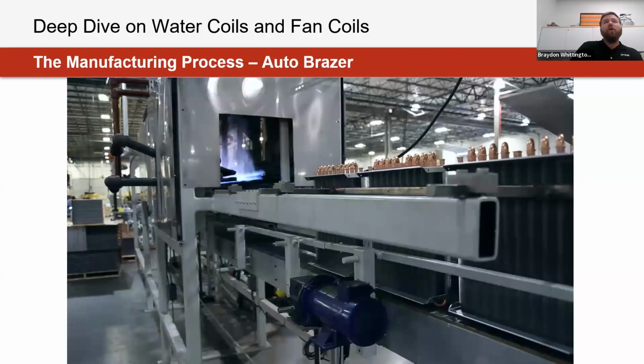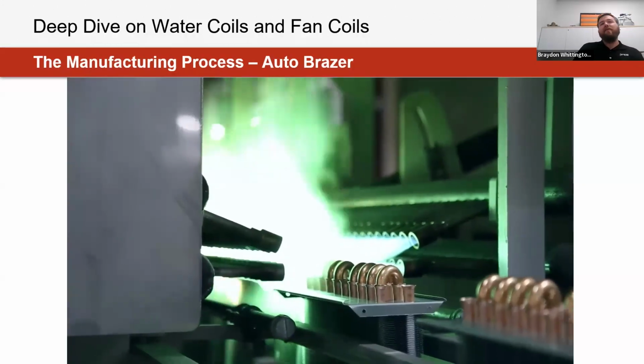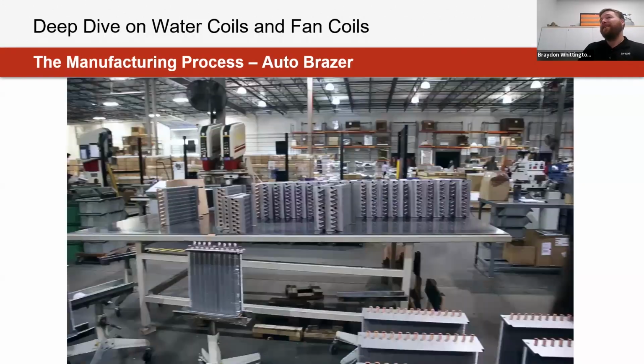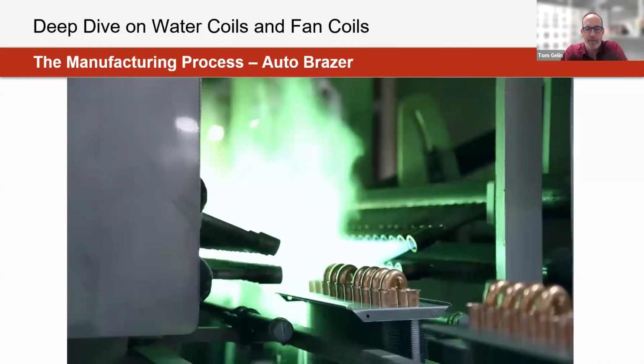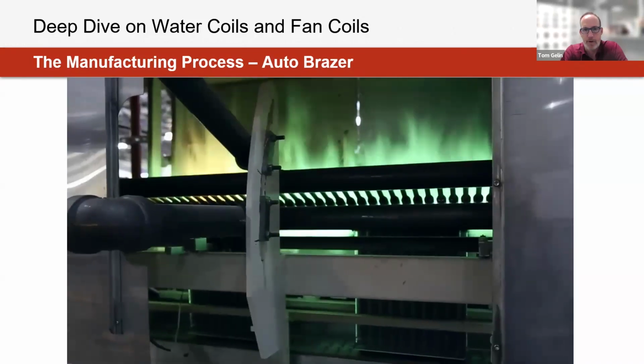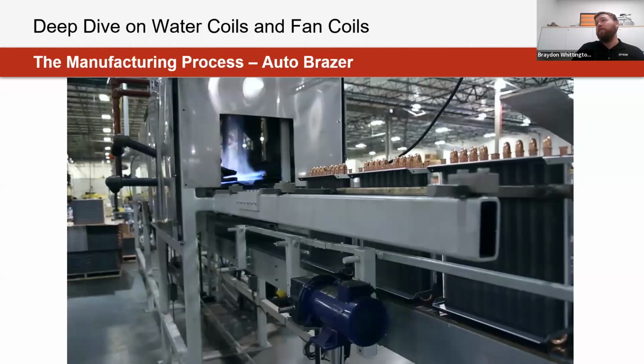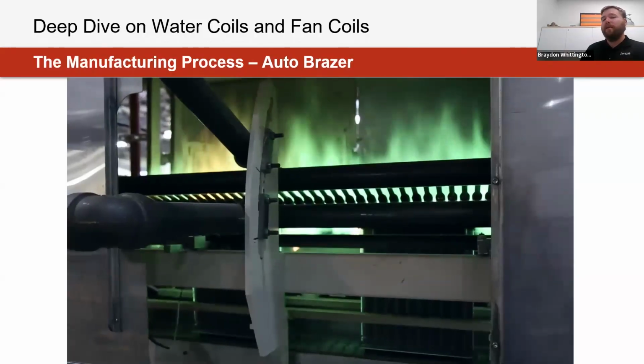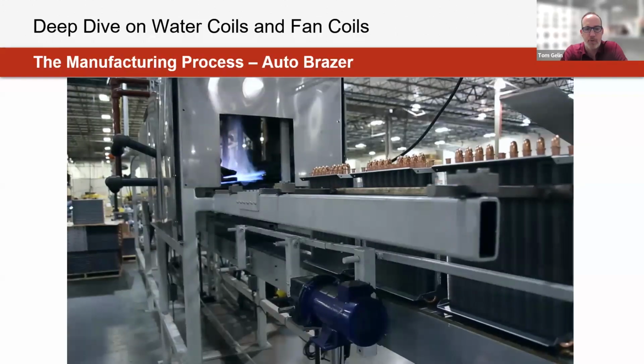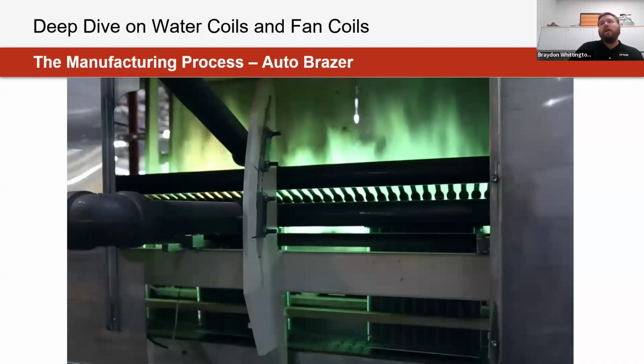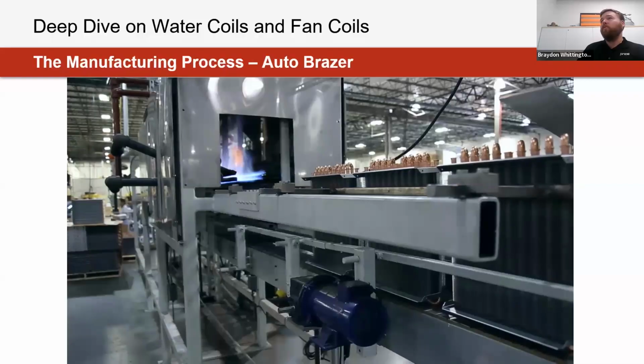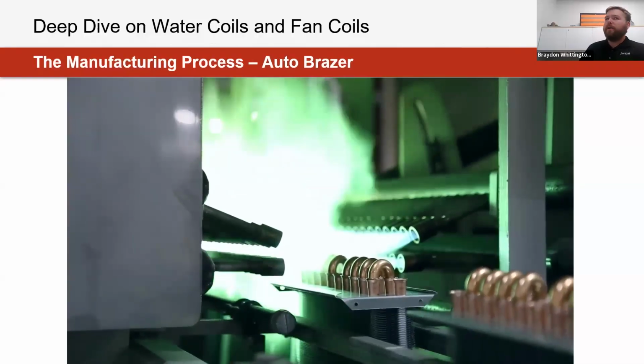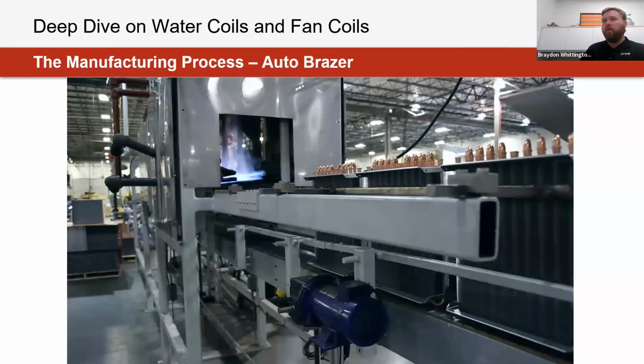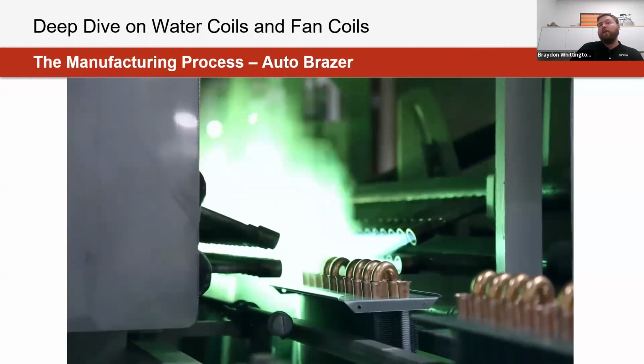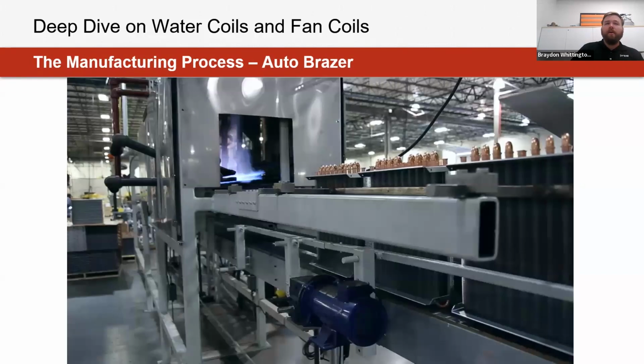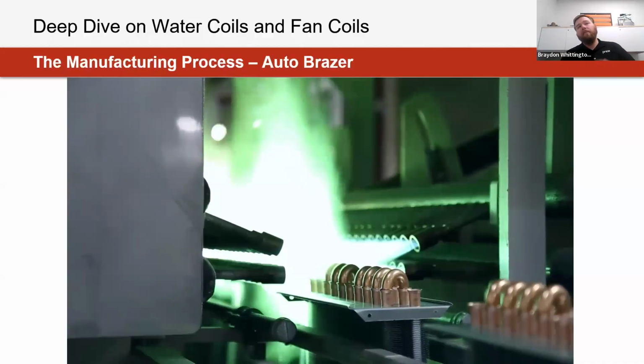Mm-hmm. Yeah, there's definitely a lot more that goes into the manufacturer level and the design time for configuring these coils. I assume you just buy something like a hairpin bender? Correct. Yeah, we're just buying some of these different pieces of equipment to put these together. Right, they're not necessarily Price originals. It's more of an equipment investment, industry standard or up to code for what you would expect for water coils made within the industry. For us right now, we just focus on reheat and cooling coils that might be paired with our equipment. There are some DX and other manufacturers you would see within the industry, but we're just not at that point for manufacturing this equipment.